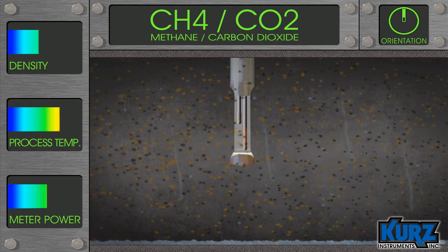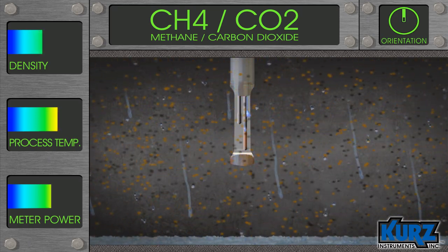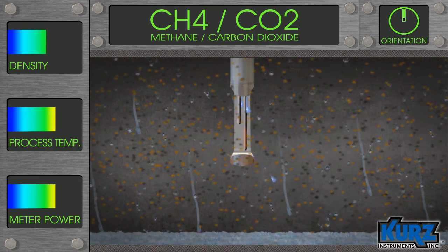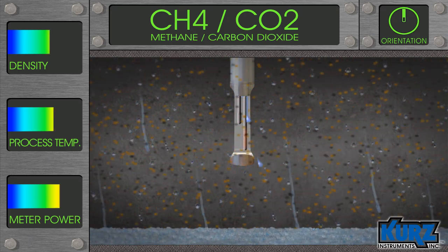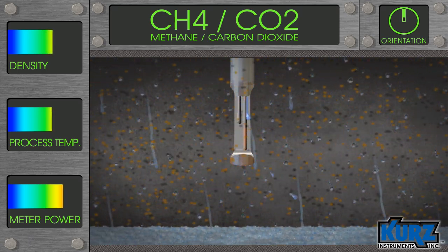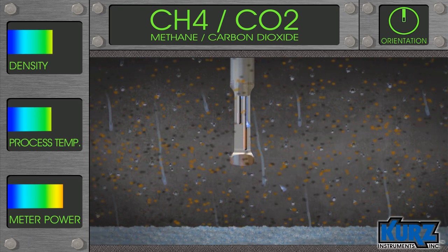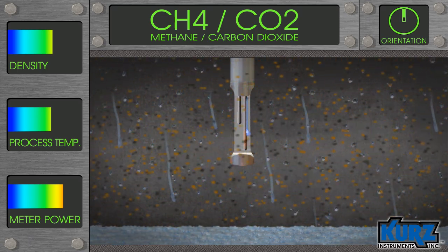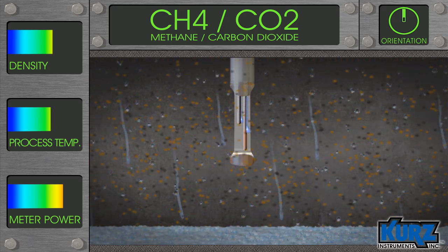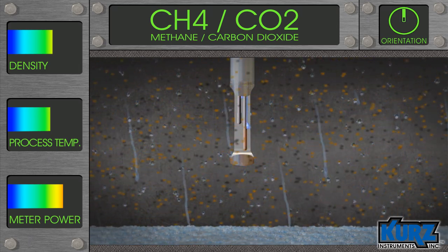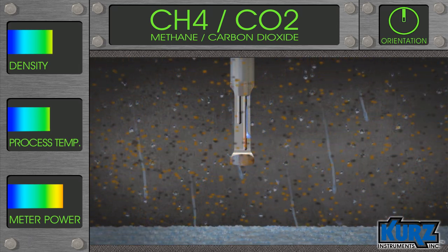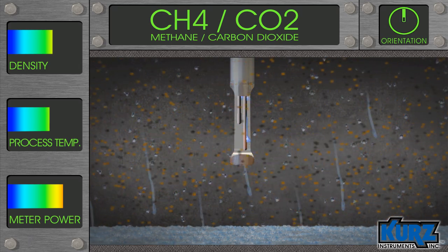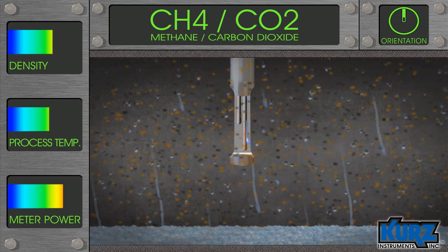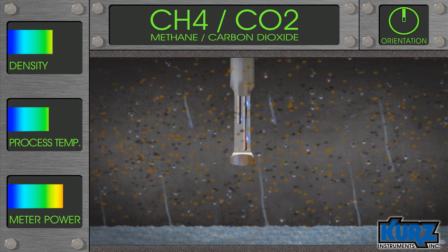Wet gas is found in digester and landfill environments. It contains mostly methane, carbon dioxide, and water vapor. Daily and seasonal cooling fluctuations commonly reduce the wet gas temperature, causing the water vapor to condense into a heavy fog. The water droplets contacting the heated sensor draw much more energy than dry gas molecules. The extra energy used to compensate for this causes a false high reading.